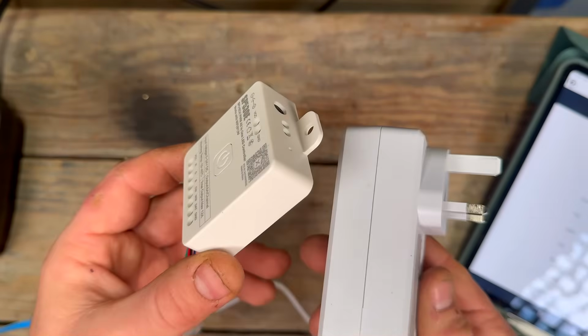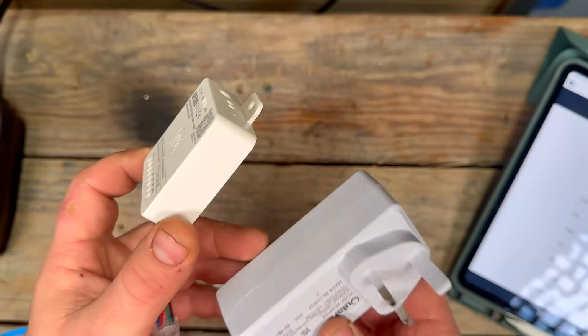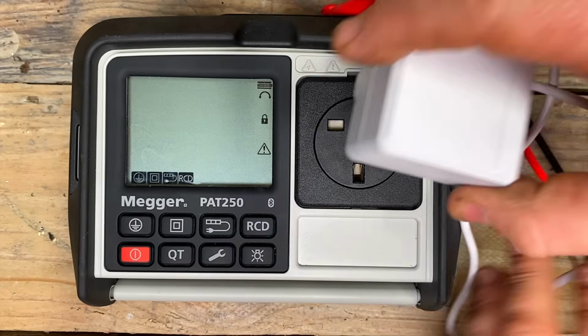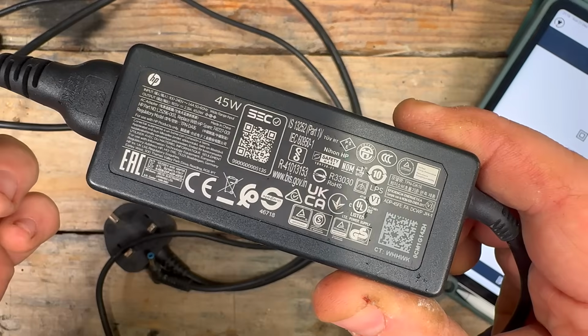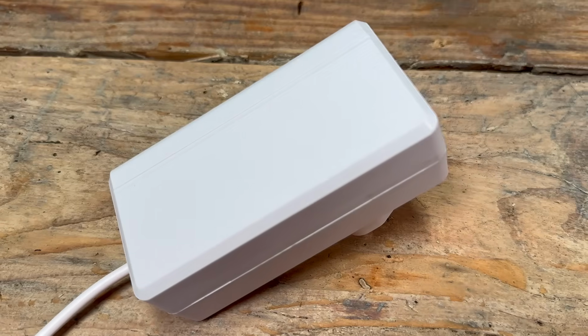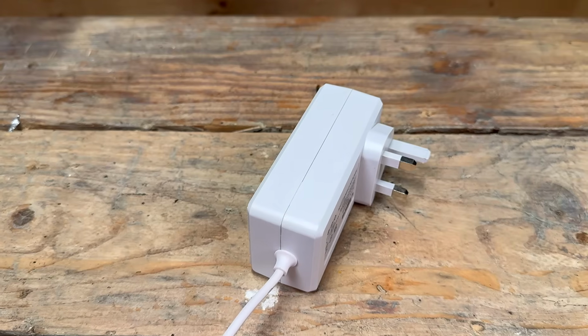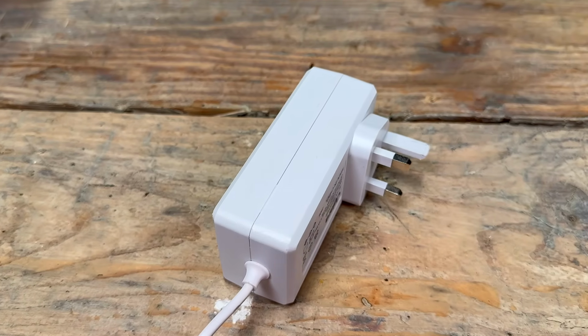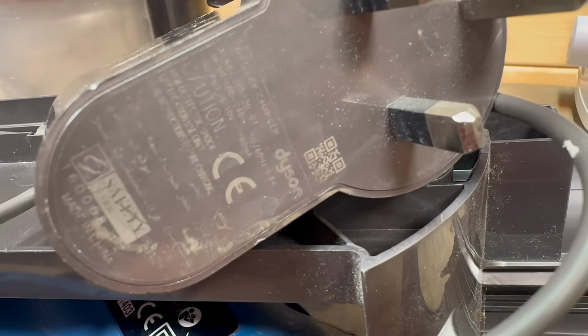Testing a separate transformer starts with a visual check. If all's good, we need to decide if an insulation resistance test is required. That's because a lot of class 3 equipment are appliances like these chargers and contain electronics, so the risk of whacking 500 volts DC or even 250 volts DC through them is not going to prove much. So a visual check might be okay.